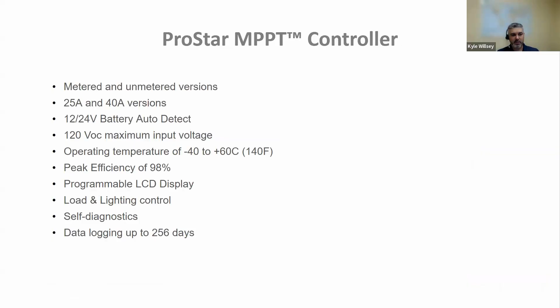Moving up to the ProStar MPPT, you have a 25 and a 40 amp output option, both at 12 and 24 volts. The input voltage ticks up a little higher to 120 volts open circuit max, and comes in both an LCD and a non-LCD option. So for field programming or adjustment of various set points, it's really a versatile controller that covers anything from about 3 to 400 watts of input power all the way up to maybe 1200 or even 1500 watts on the high end.